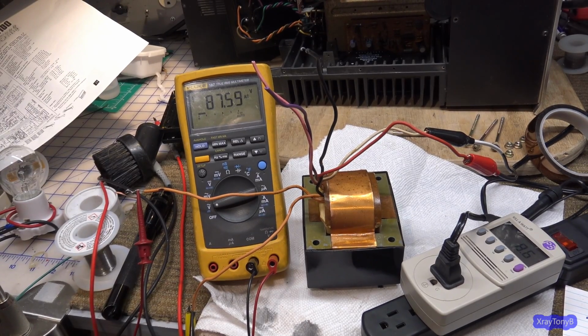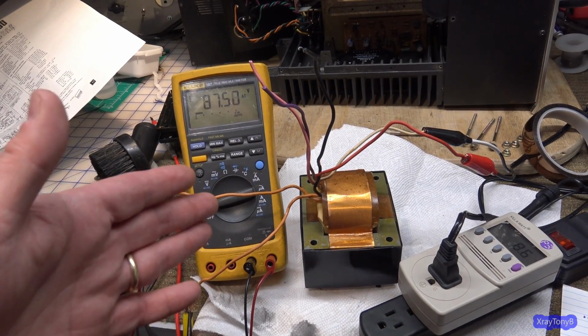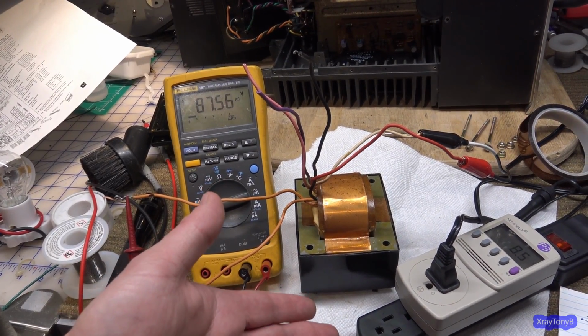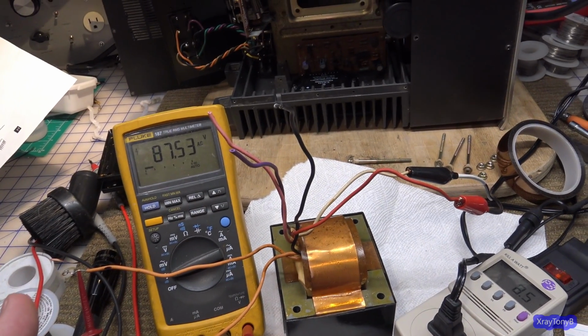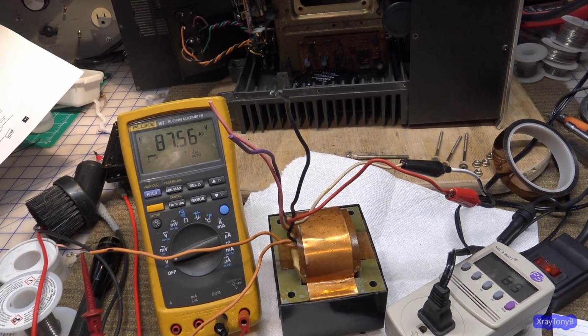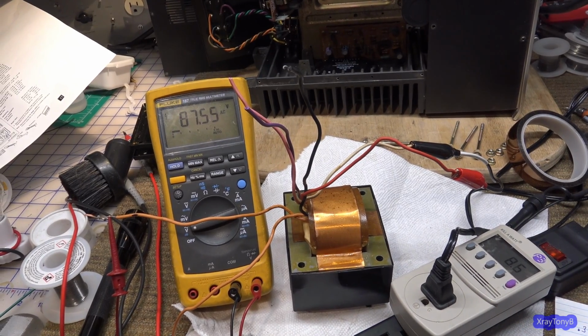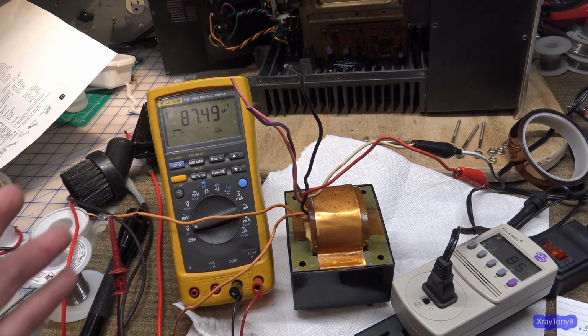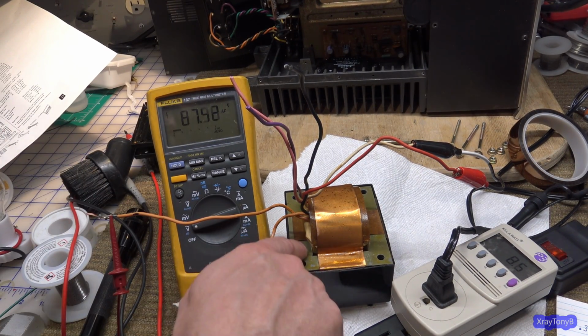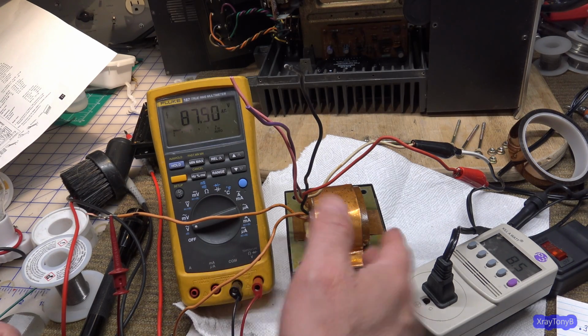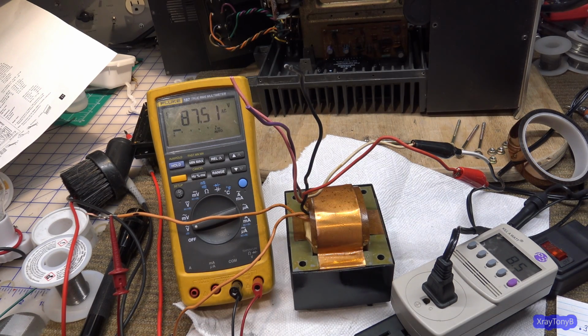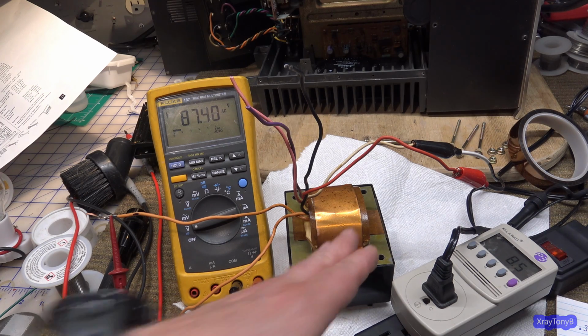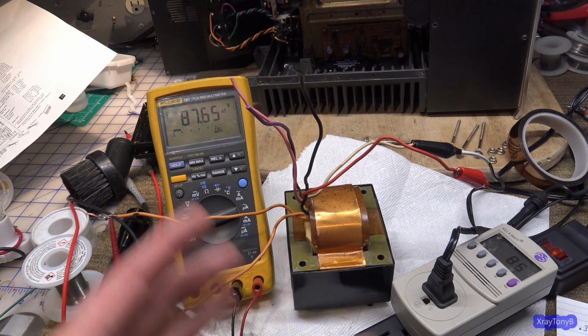So, long story short, this is a good transformer. I don't think there's any problems with it - it was just that thermal fuse that popped open. I don't see any discoloration, nothing that makes this look like it got too hot. Normally this varnish would discolor, turning a real dark brown color when these transformers run really hot and overheat.